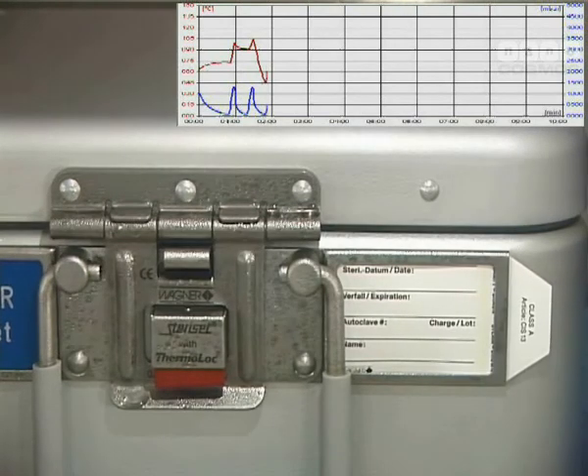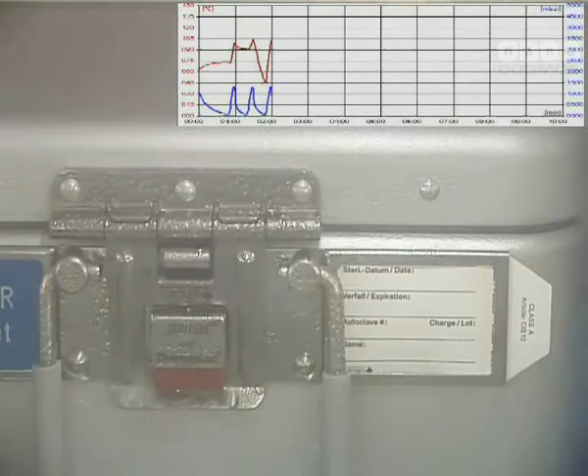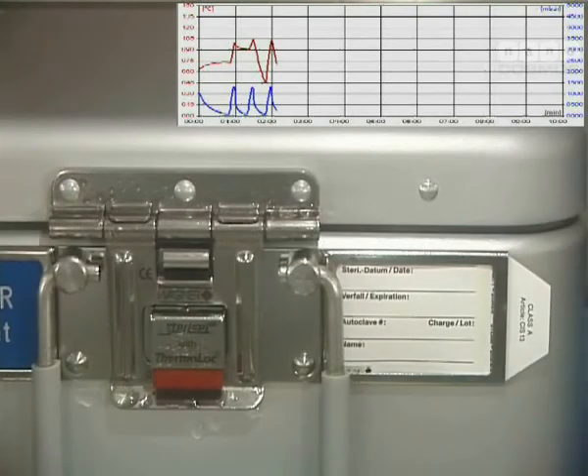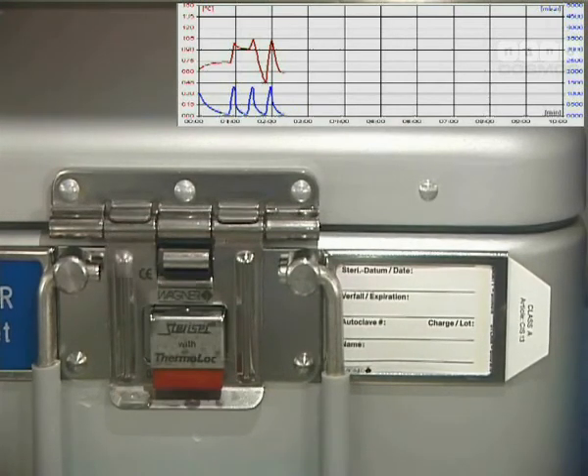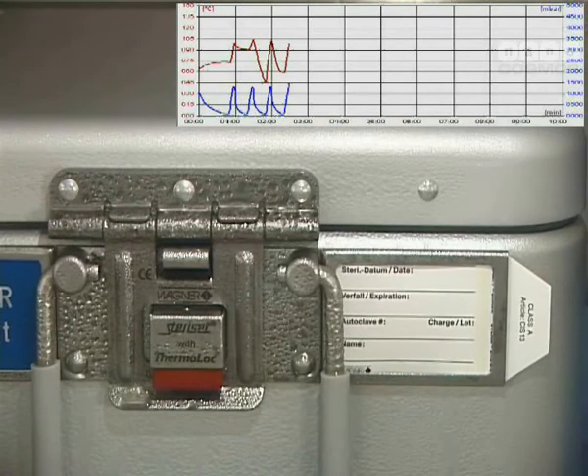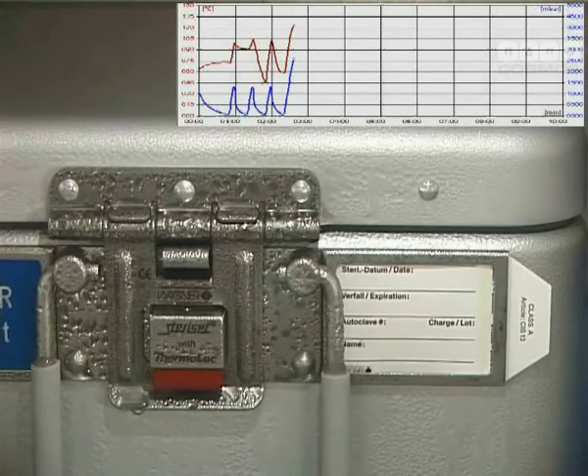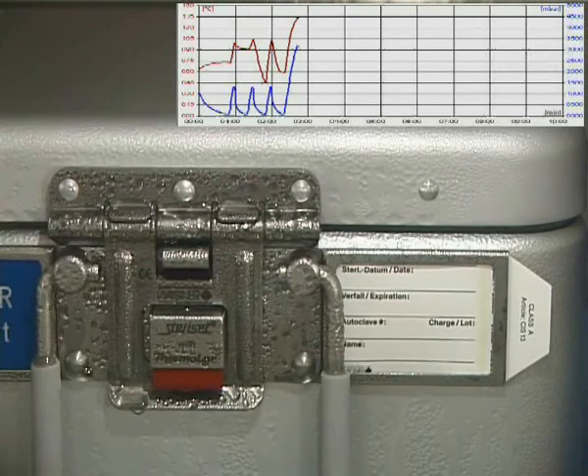The next pulse is, in addition, adding more temperature and removing air, remaining air from the cycle. So that after the next and the third pulse, typically in Europe and in most cases in the US, you use three pulses. After the third pulse, you fill in steam to finally reach the exposure level, the high temperature, high pressure level, 134 degrees Celsius or 270 Fahrenheit.